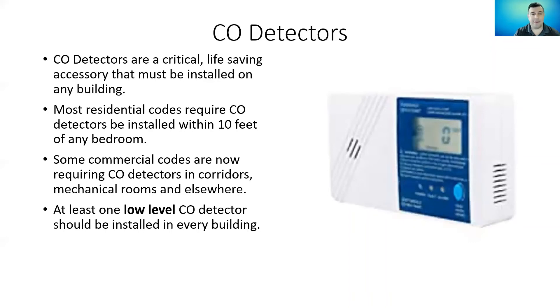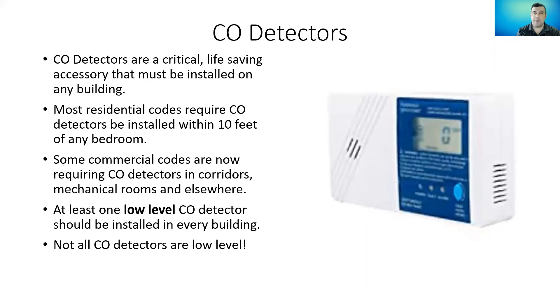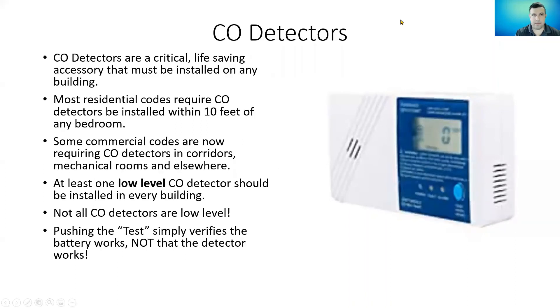At least one low-level carbon monoxide detector should be installed in every building. A low-level carbon monoxide detector is one that very quickly detects and alerts in the presence of carbon monoxide. Not every carbon monoxide detector you purchase is a low-level one — the listing requirements for carbon monoxide detectors are actually not very safe, as we'll discuss. It's also important to realize that the little test button on every carbon monoxide detector you buy from the store does not test whether it's actually detecting carbon monoxide — it is simply telling you that the battery is not dead yet.